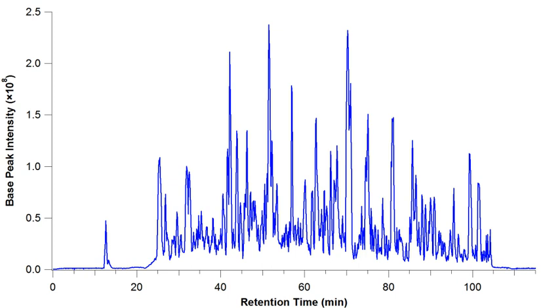This means that the base peak chromatogram represents the intensity of the most intense peak at every point in the analysis. Base peak chromatograms often have a cleaner look and thus are more informative than TIC chromatograms because the background is reduced by focusing on a single analyte at every point.